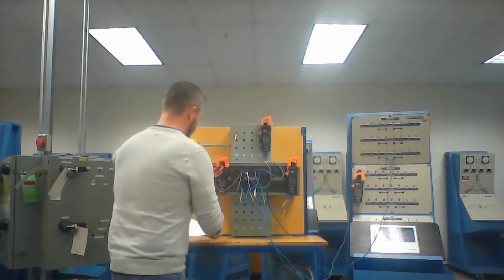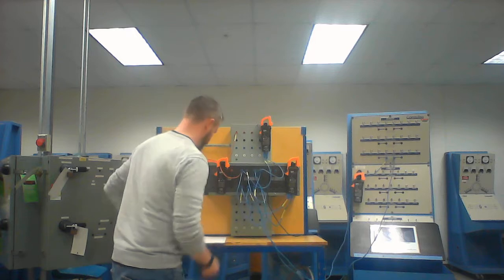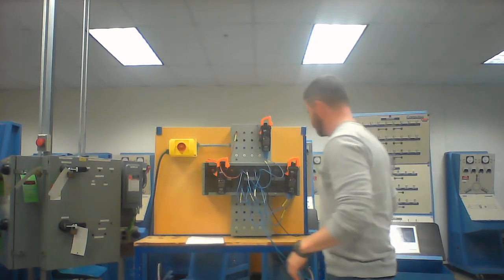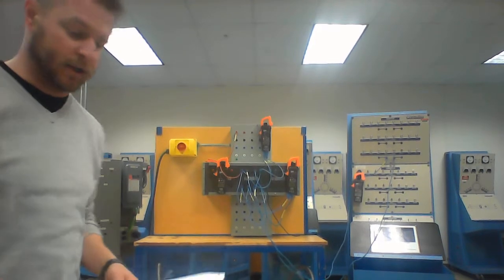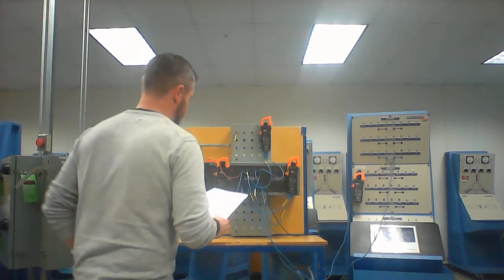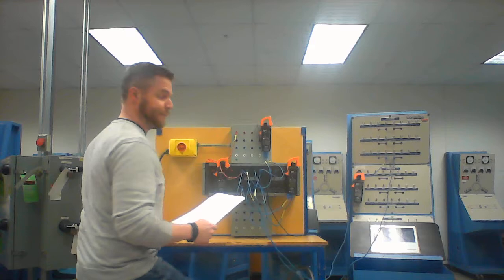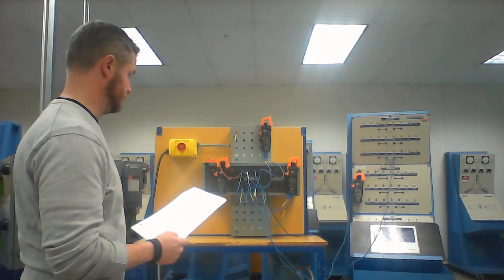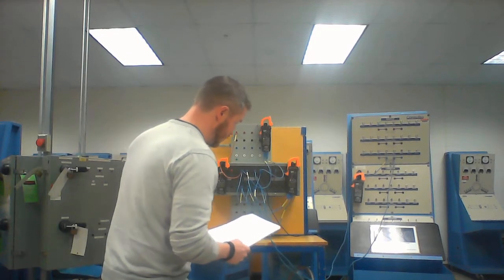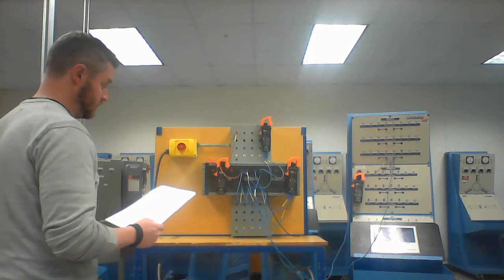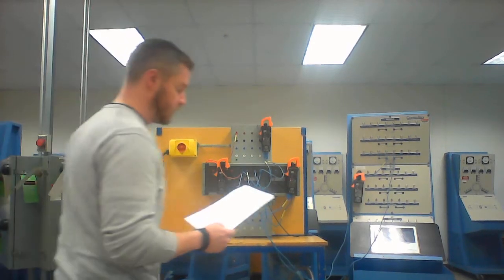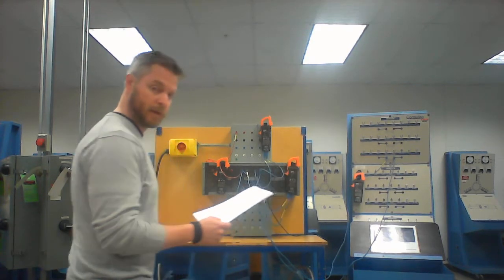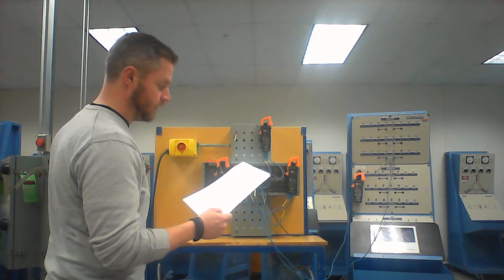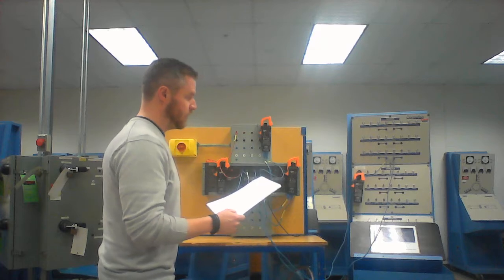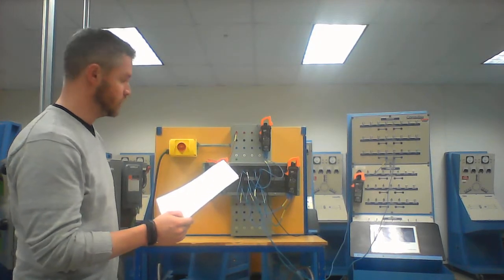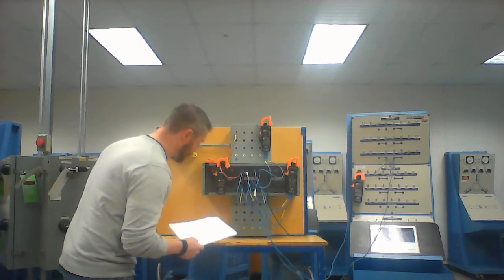Okay, step number 1: put in the 220 ohm resistor. And we'll start taking some readings. My primary voltage at 220 ohms of load, 203.5. Secondary voltage, 122.8. We'll do calculated voltage ratios later. Okay. Excitation current, that's still going to be your 100 milliamps, your 0.12, 0.11. Your measured secondary current flow, 0.51 amps. And measured primary current flow, 0.36 amps.